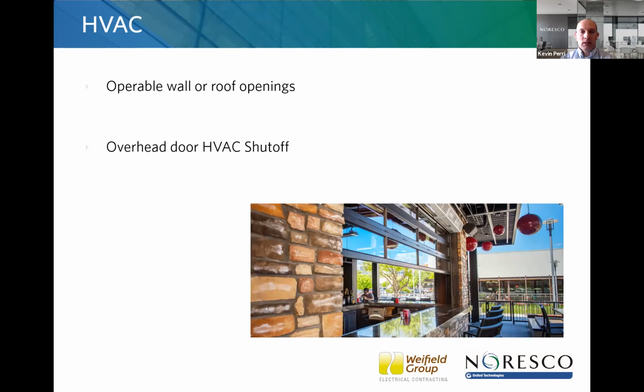Another item under the HVAC, if we all enjoy these operable windows and these overhead doors that we see like on the picture, when we're going out to a restaurant and whatnot. Sometimes these are cargo doors, sometimes these are accordion style doors, loading dock doors. All of those items fall into this category of overhead door HVAC shutoff. And that's saying that all the HVAC systems, whether it's heating, cooling, or humidity, have to turn off in that zone when that overhead door is open to 25% or more. So you can see in the photo, that looks to be about 50%. So all the HVAC associated with that zone would be turned off because it's opened over 25%.